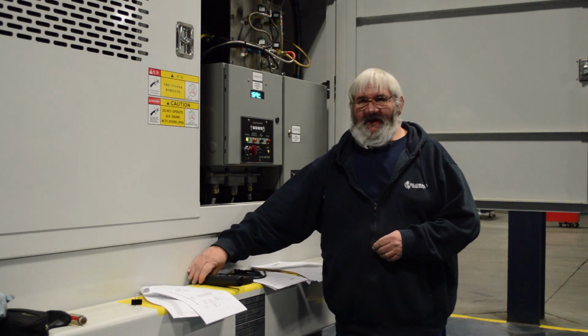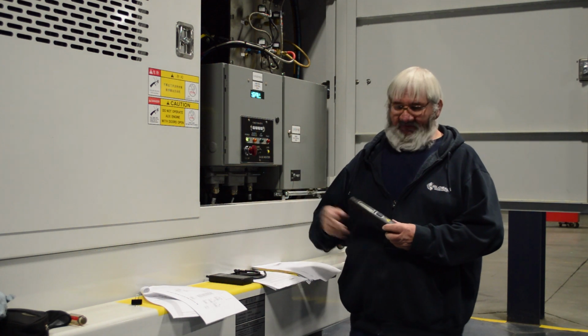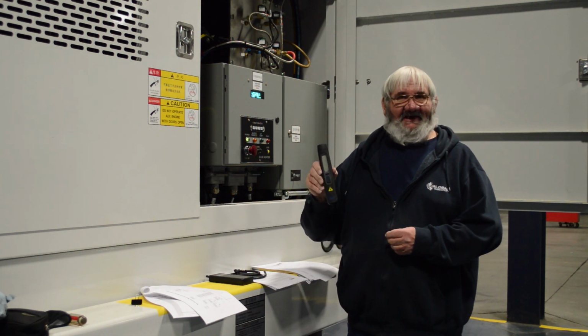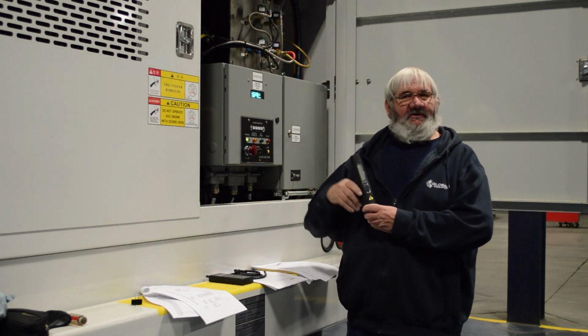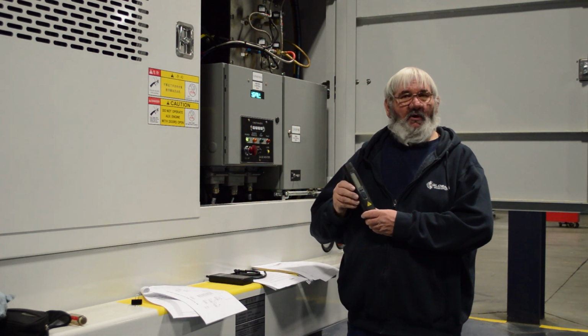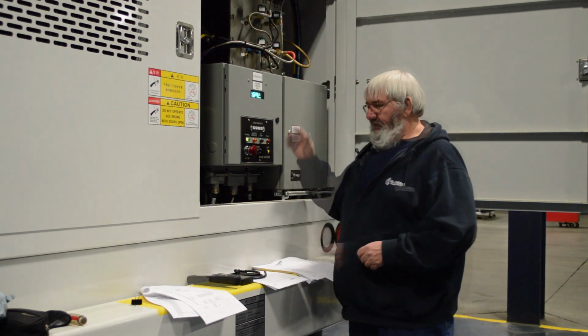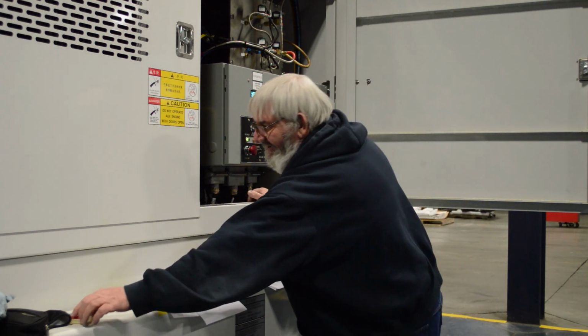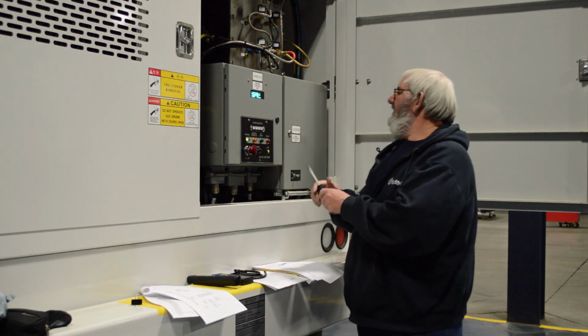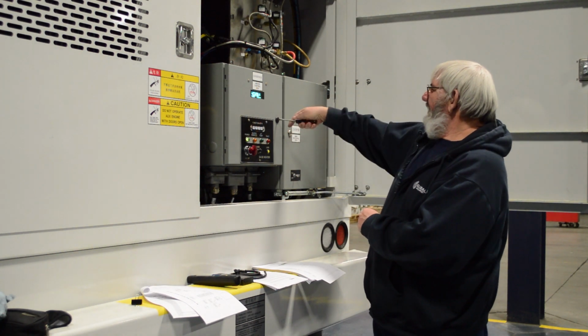The other thing that will help you in troubleshooting a blower problem is your photo tach. Here again, this is where you would measure your blower RPM, with a digital photo tach. To measure the air pressure, we would open the box.